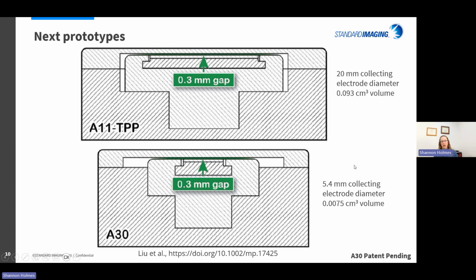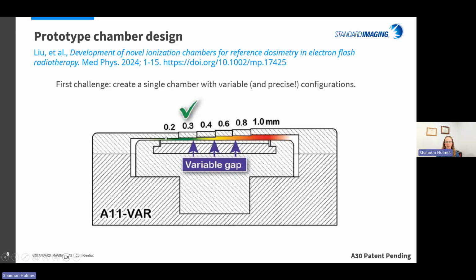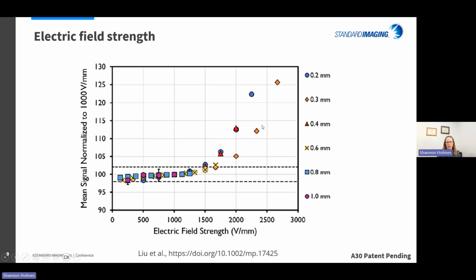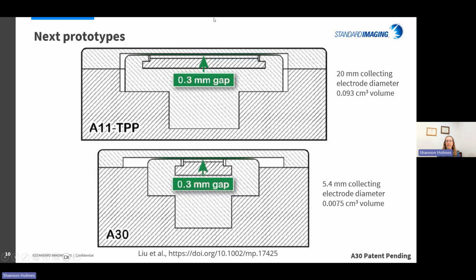So the next prototypes that we made, one with just the fixed gap, not replaceable, at 0.3 millimeters. In going back to this variable gap, the 0.2 was just a little bit too tight in terms of the manufacturing tolerances. 0.3 was kind of the Goldilocks spot where we got really good response, but we could construct it well. And once we got higher than that, the behavior of the chamber was not quite where we wanted it to be. So we made that A11 thin parallel plate.